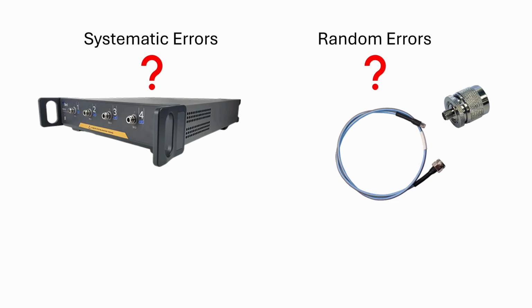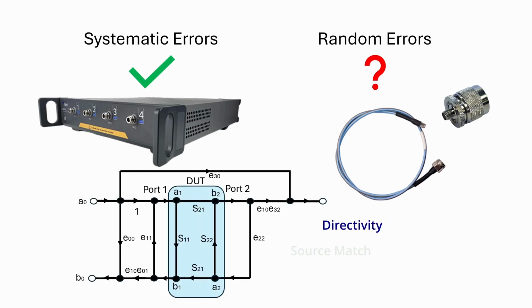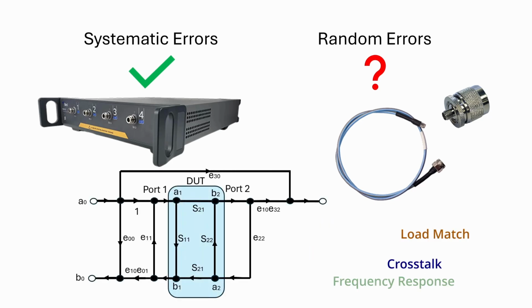A two-port calibration is used on a vector network analyzer to help improve measurement quality, primarily by eliminating systematic errors that may be due to imperfections in the VNA itself as well as some portions of the test setup. This will enhance specifications around such things as directivity, source match, load match, crosstalk, and frequency response in both the forward and reverse directions, and helps provide more accurate S-parameter measurements, leading to better transmission loss and reflection insights.